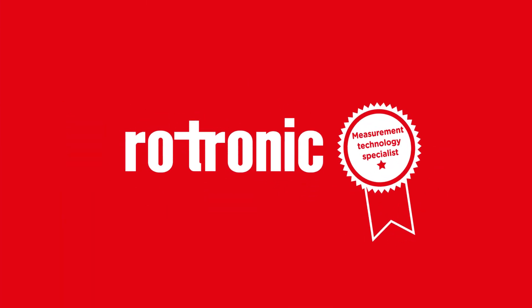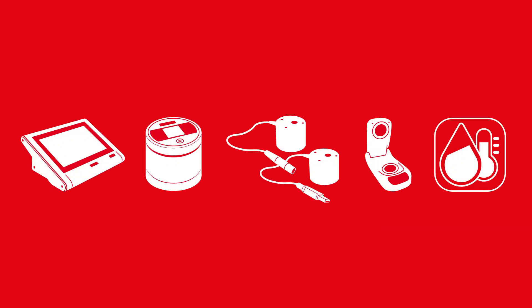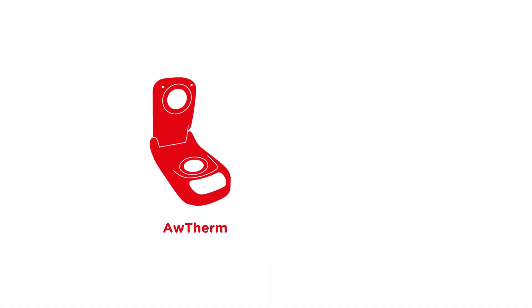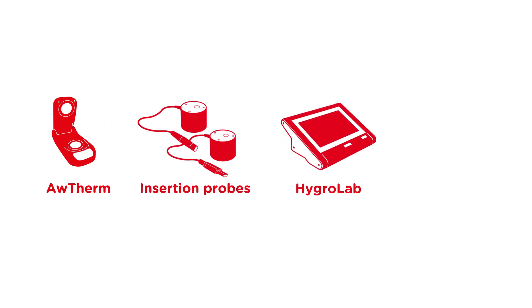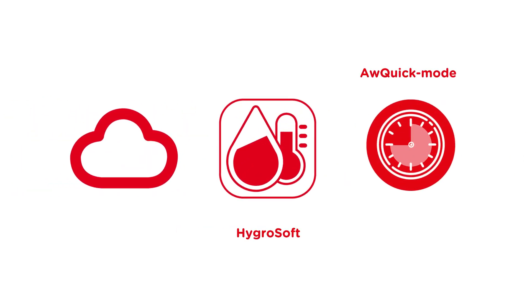As a leading specialist in measurement technology, Rotronic offers a wide range of highly precise devices for measuring water activity. They can be easily combined with one another to suit user requirements. The Rotronic range includes the high-end temperature-stabilised laboratory analyser, various probe types, the bench-top instrument and the portable handheld device. Thanks to the integrated AW quick mode, the water activity can be measured rapidly.